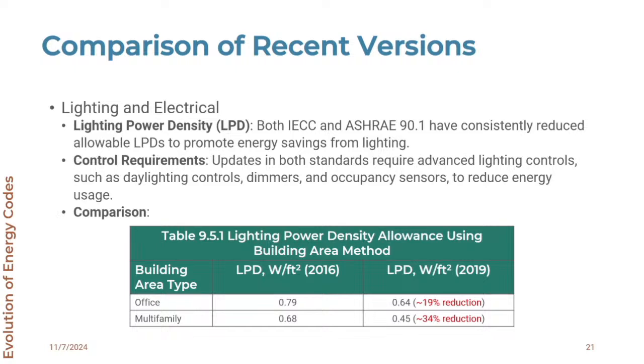The reductions here are pretty staggering. This example uses the building area method, looking at an office building as a whole rather than the space-by-space method, which looks at individual space use requirements and dictates what LPD is allowed for those spaces. You'll see almost a 20% and a 35% reduction in just these two categories alone.